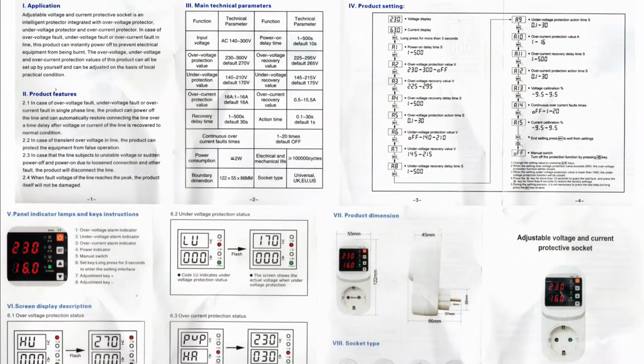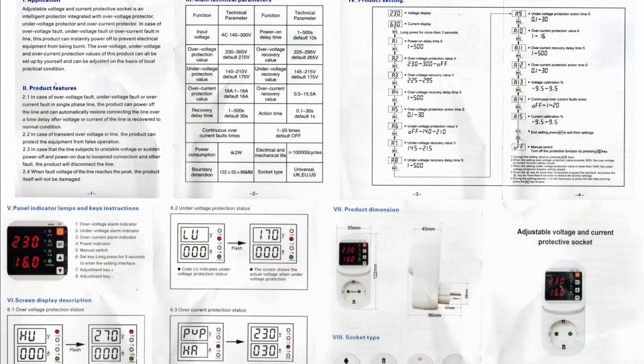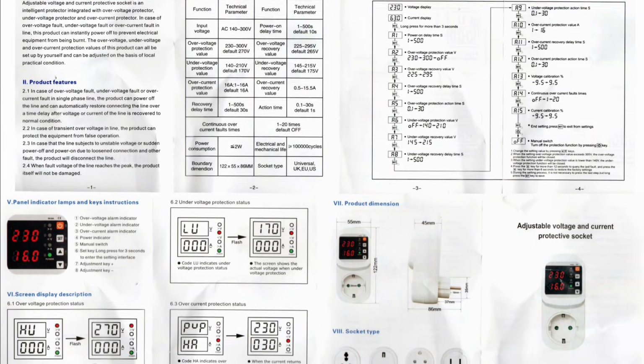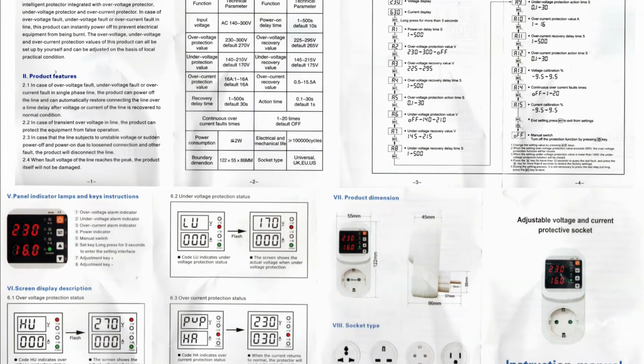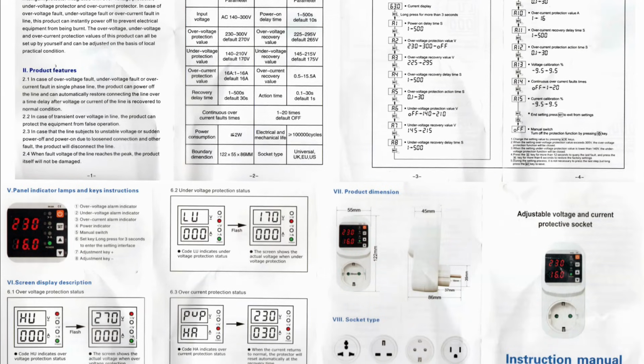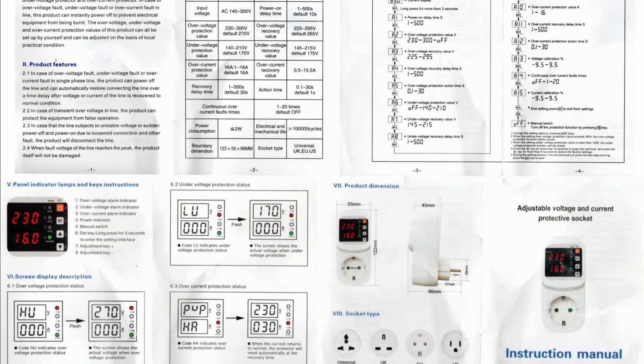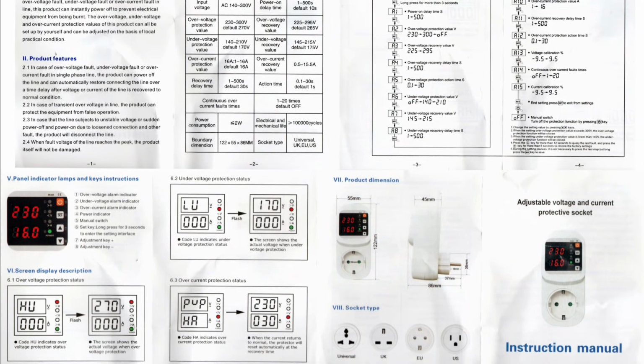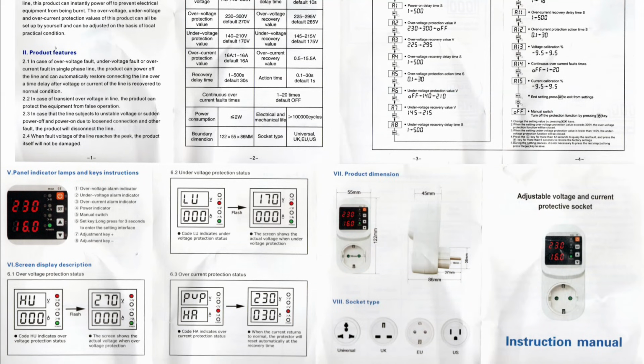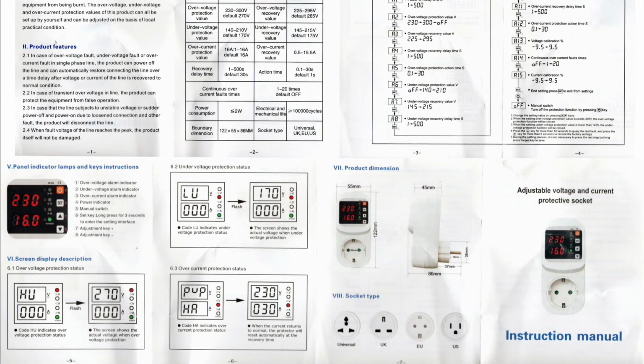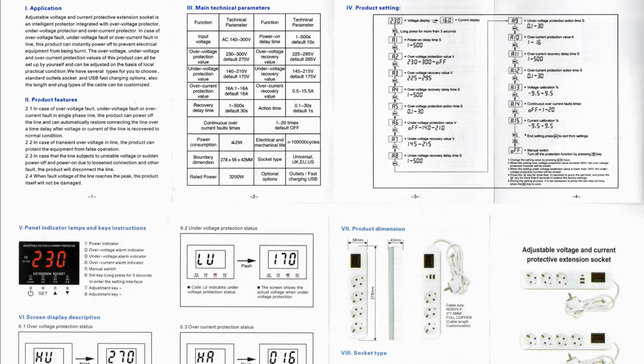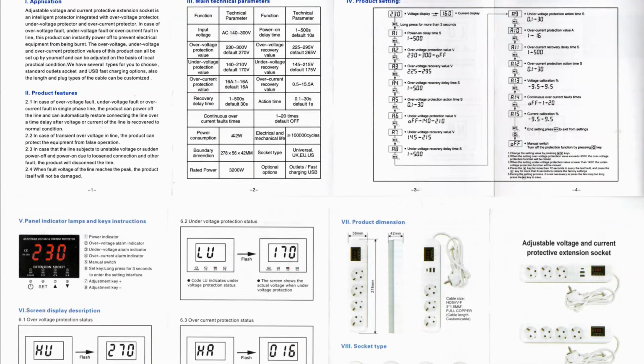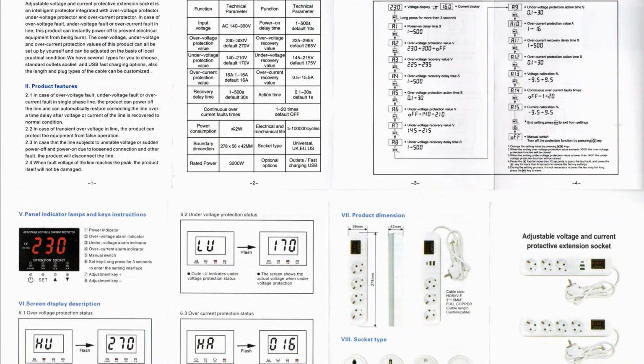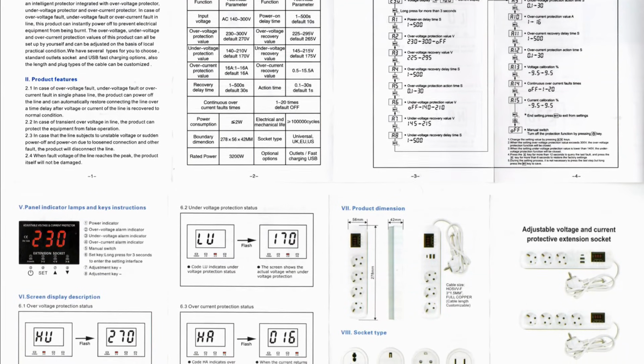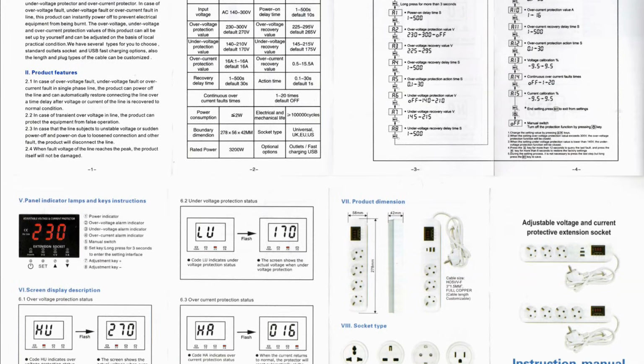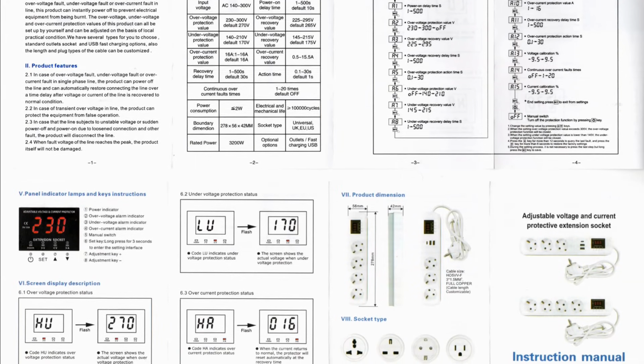The instructions for both devices are quite detailed and describe the operating principle of the relay. They outline the main protection functions, overvoltage and undervoltage, overcurrent, as well as automatic power restoration. It is separately shown which LEDs light up when a particular protection is triggered. The instructions also describe the settings menu in detail. Here you can set the voltage and current trip thresholds, the delay time for switching on and restoration, and also perform calibration of the readings.